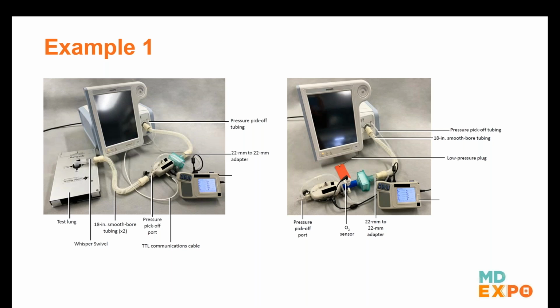But there's a few things that you might not quite be able to see here, like if you look closely, there's a pressure that's been teed into the analyzer here. If you look at this photo, you'll see that they've teed in an oxygen analyzer. So when you're doing your testing, you have to make sure that you have all the components that you need, and you need to understand your device so that you know how to apply it for all the tests that they're asking you to do.